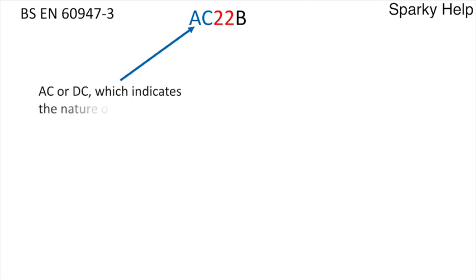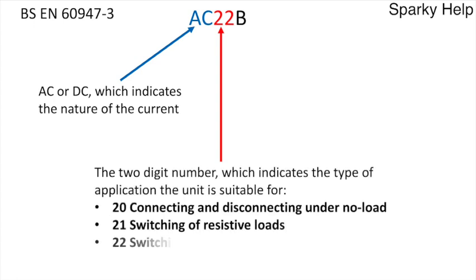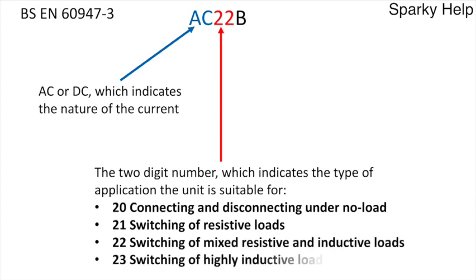Now we've had these numbers on the front — AC22B as an example. What do they all mean? The first part — AC or DC — means it's an AC or DC type switch. If it's DC, the manufacturers will make the contacts to a slightly different standard because of the nature of the current. The second number can be 20, 21, 22, or 23. In this case it says 22, so it's switching of mixed resistive and inductive loads.